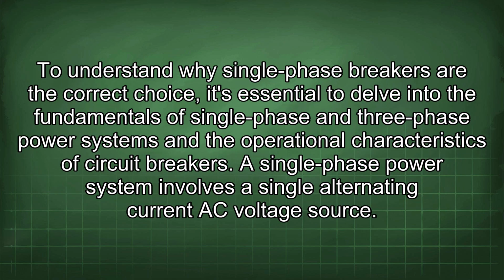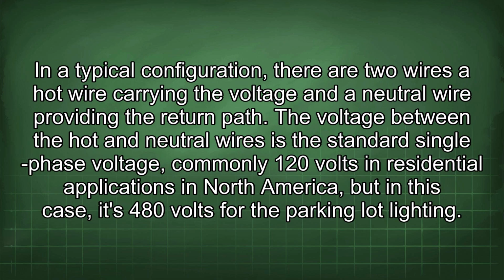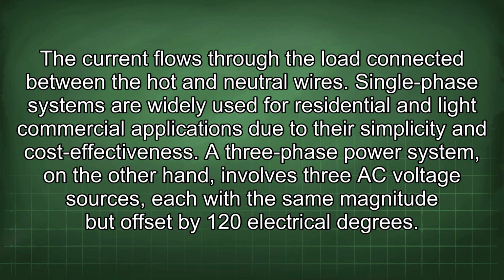To understand why single-phase breakers are the correct choice, it's essential to delve into the fundamentals of single-phase and three-phase power systems and the operational characteristics of circuit breakers. A single-phase power system involves a single alternating current AC voltage source. In a typical configuration, there are 2 wires, a hot wire carrying the voltage and a neutral wire providing the return path. The voltage between the hot and neutral wires is the standard single-phase voltage, commonly 120 volts in residential applications in North America, but in this case, it's 480 volts for the parking lot lighting. The current flows through the load connected between the hot and neutral wires. Single-phase systems are widely used for residential and light commercial applications due to their simplicity and cost-effectiveness.